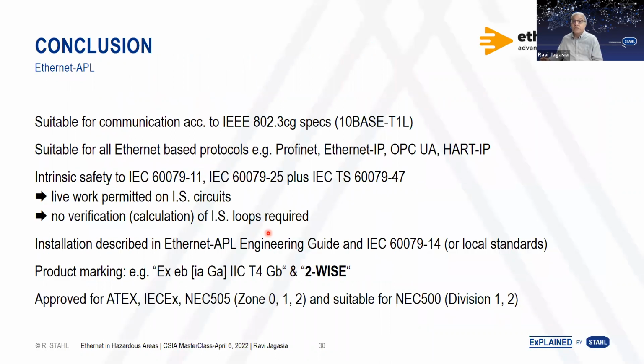So in conclusion, you now have a standard with Ethernet-APL, which adheres to the standard 10BASE-T1L. It's just a variant there for hazardous area. Is good enough for all the Ethernet or IP-based protocols. So currently, PROFINET, EtherNet/IP, OPC UA, HART-IP, and anything else that may come in the future. It has intrinsic safety conforming to -11, -25, and -47, which will allow you to do live work because it is an intrinsic safe circuit, which definitely means a good or a quick uptime in your plants, an easy maintenance process. You don't need to be worried about entity parameter calculations before you put a field device connected to the Ethernet-APL network. You have the Ethernet-APL engineering guide to help you design this.